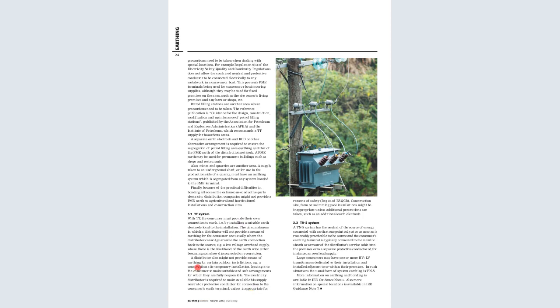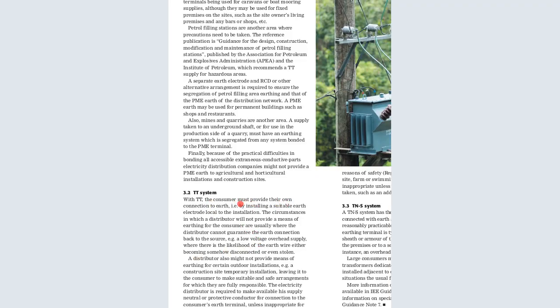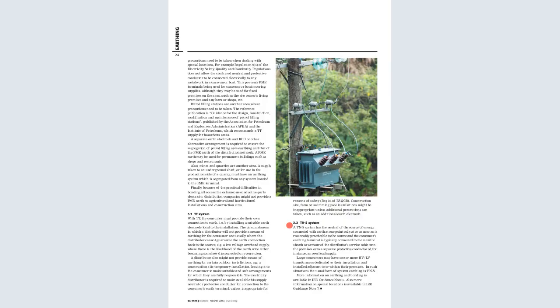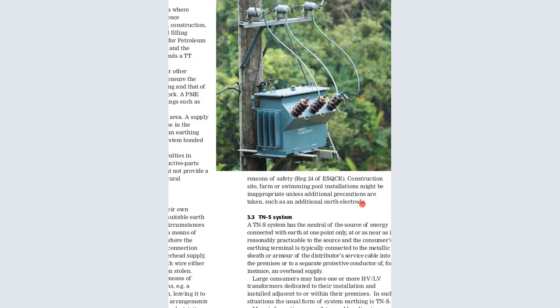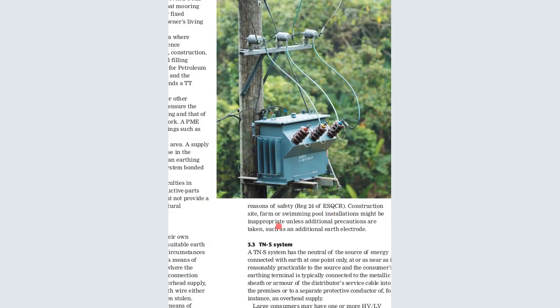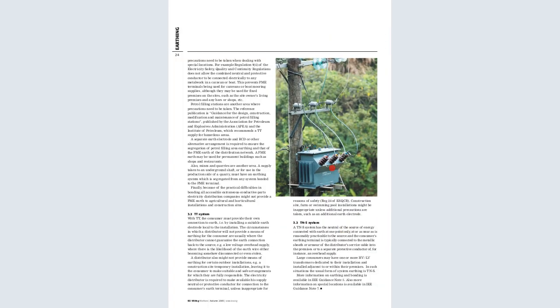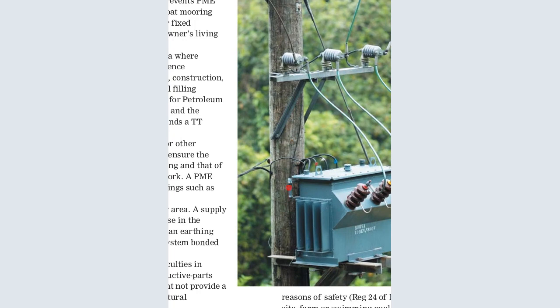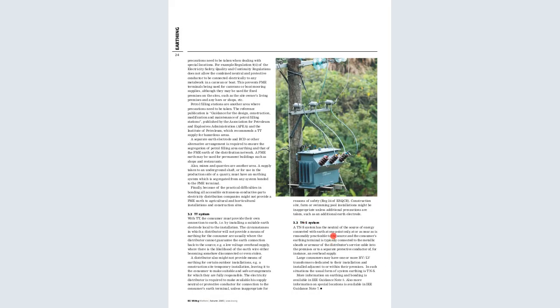So these are the systems that we talked about. The TT system we talked about is where the consumer must provide their own connection to the earth by installing a suitable earth electrode local to the installation. The circumstances in which the distributor will not provide the means of earthing for the consumer are usually where the distributor cannot guarantee the earth connection. And then we have the TNS system. You can now see an example here. This is a construction site farm. A swimming pool installation might be inappropriate unless additional precautions are taken. Now, in case we have a transformer there, the PME has to be given. You can see there's a cable that runs here. This is the PME, the one that connects to the earthing.